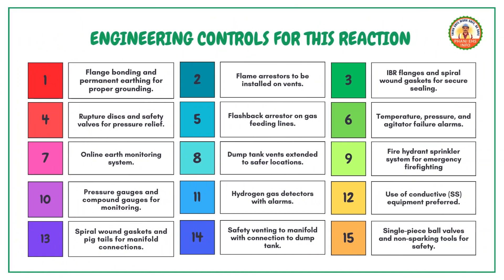Engineering controls. To ensure safety, implement the following engineering controls: flange bonding and permanent earthing for proper grounding; flame arresters installed on vents; IBR flanges and spiral wound gaskets for secure sealing; rupture discs and safety valves for pressure relief; flashback arrestor on gas feeding lines; temperature, pressure, and agitator failure alarms.